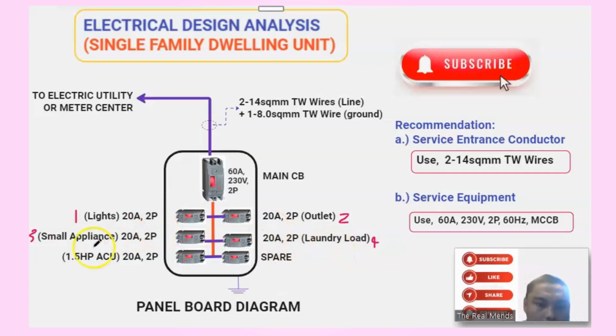So for the 1.5 HP ACU, yung kanyang pole current is 10 amperes. So fit pa rin siya sa 20 ampere trip na circuit breaker. Or pwede kang maggamit ng 30 ampere trip. So depende sa supplier. Okay, circuit number 5. And then for circuit number 6, we have the spare. So for future loads, ano pang idagdag mo sa future.